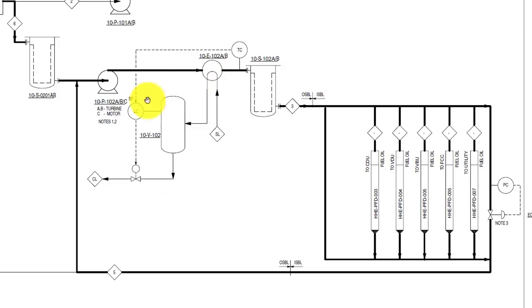You can see the temperature control loop also. Here you can see the battery limit of ISBL and OSBL. Fuel oil is supplied to various ISBL units' furnaces. On the ISBL side, you can see that one pressure control valve is given, which ensures constant pressure in the fuel oil loop.